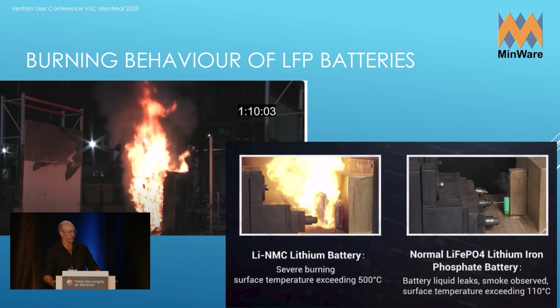When batteries catch fire, they tend to be quite spectacular - lots of flame, flaring and explosions. A fully charged battery will typically be more volatile than an uncharged one. But in terms of total heat released, it doesn't really matter if the battery is charged or not - the electrolytes really drive a lot of the heat. So while a fully charged battery might be more spectacular, the same amount of heat comes off the battery whether it's fully charged or not.